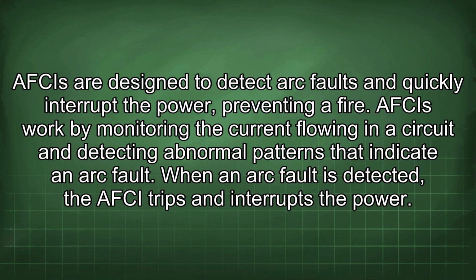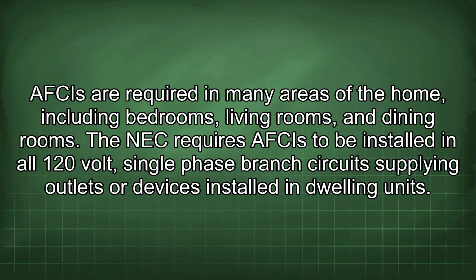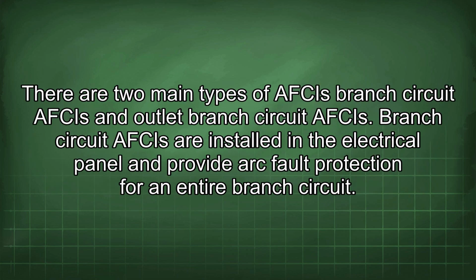AFCIs work by monitoring the current flowing in a circuit and detecting abnormal patterns that indicate an arc fault. When an arc fault is detected, the AFCI trips and interrupts the power. AFCIs are required in many areas of the home, including bedrooms, living rooms, and dining rooms. The NEC requires AFCIs to be installed in all 120-volt single-phase branch circuits supplying outlets or devices installed in dwelling units. There are two main types of AFCIs: branch circuit AFCIs and outlet branch circuit AFCIs.